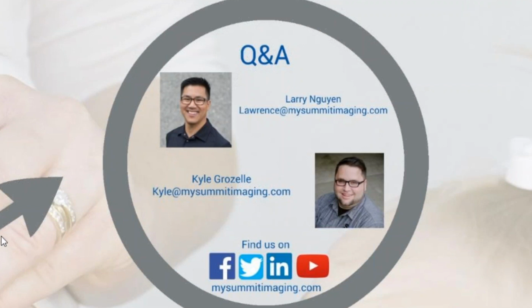Kyle here again. In terms of TEE probes, the timing is a little tricky, since these probes really should be tested after every use using a leakage tester and visually inspected. But going in a PM direction, I would say that is a situation where a biomed can go in and maybe do an image quality test and just verify the functionality of the probe. It would be preferred every quarter, using something similar to the ACR PM checklist, where you're checking for depth and clarity of image, and then performing a visual inspection beyond what maybe infection control would see. If you could even bring that down to a month, it would be ideal, but I know these hospitals are starting to get really pushed for time. And ultimately, you might see the transducer more often than that, just based on use, if your infection control team is catching the small bites and punctures quickly.